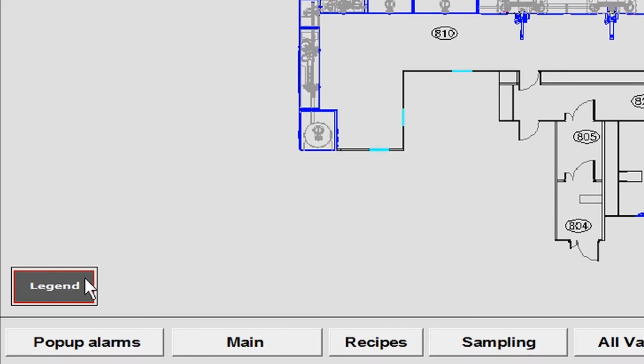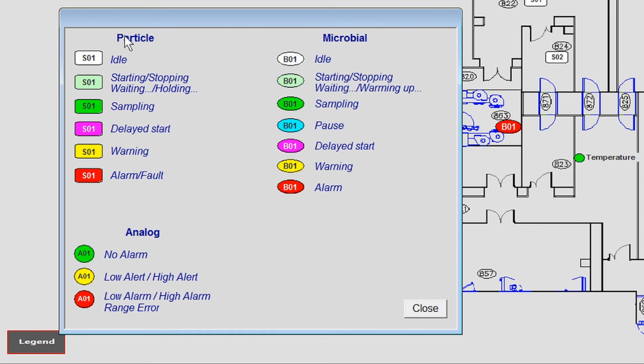The legend has predefined symbols and shapes for particle, microbial, and analog outputs for use with items such as light towers. Additionally, for each sensor, the color defines the activity of those sensors. These include idle, starting, stopping, waiting and holding, sampling, delayed start, warning, and alarm or fault conditions.